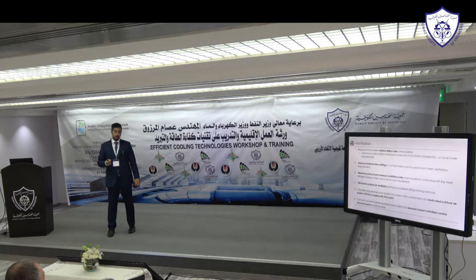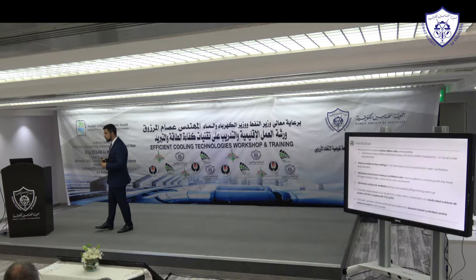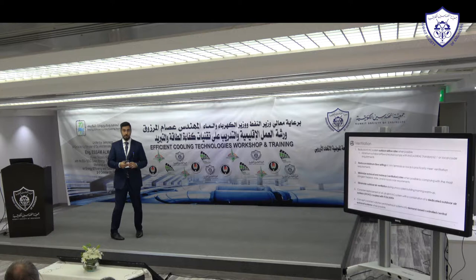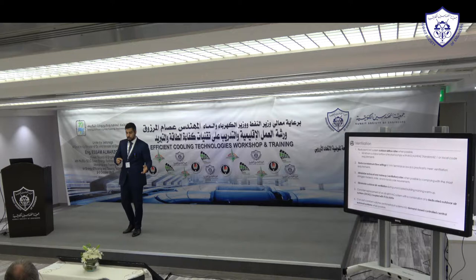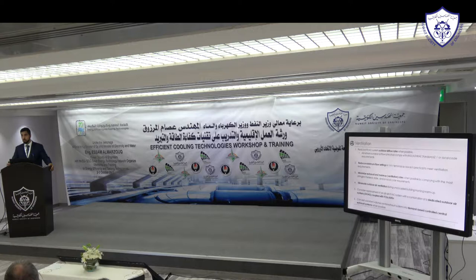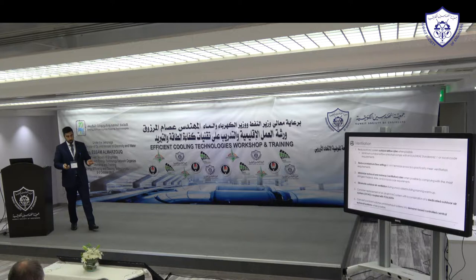Convert constant volume central exhaust systems into demand-based control ventilation systems. For example, in a conference room with varying attendance, you can add CO2 sensors to detect CO2 parts per million and send a signal to the controller to reduce fresh air to the level needed. You can also add a door counter to know exactly how many people are inside and connect that control to the fresh air handling unit to reduce incoming fresh air to requirements.